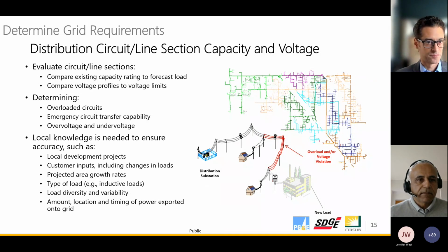Then we get a little more granular - we go down to the circuit level, the line section level of a feeder. We evaluate those line sections' capacity versus the forecasted load. We also compare the voltage profiles to the voltage limits we have to maintain on the system. We determine overloaded circuits, overloaded line sections, and what happens during power outages when we need to restore customers - emergency circuit transfer capability. During an outage or a clearance to do work, we need to be able to move load around from one circuit to another, and we need to look at that as well.